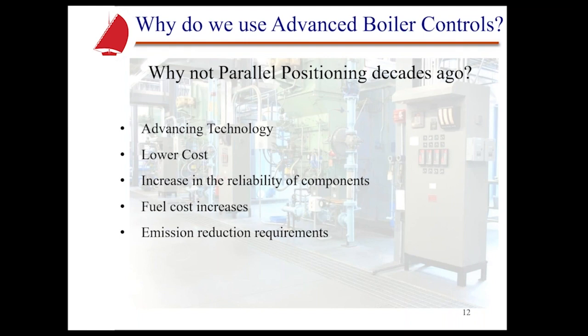And the reason we're doing it is fuel costs. The fuel costs have increased so much over time and will continue to increase. That's not going to be changing. And a lot of that cost increase comes because emission reduction is required. And that's also going to continue to tighten. So having a control that can absolutely maintain perfect combustion across a firing rate range is really a plus, and those emission reductions can be measured, and it's exactly what we need to achieve.